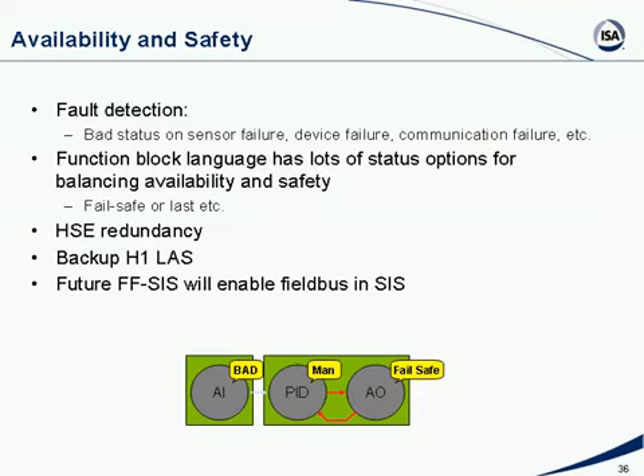In these function blocks, there are lots of options you can configure to balance safety and availability. Do you want it to fail safe in case of a communication failure, or remain in the last position? And once communication recovers, should control continue or recover, or should it remain shut down? Lots of options.